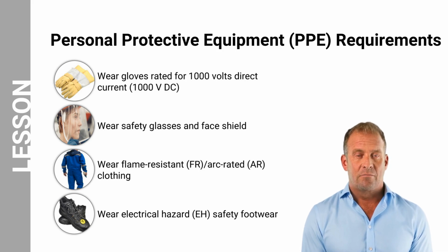Let us now look at the requirements to ensure you are safe when working on high-voltage systems. Wearing appropriate personal protective equipment that includes gloves rated for 1,000 volts direct current, safety glasses and face shield, flame-resistant and arc-rated clothing, and electrical hazard safety footwear is crucial to ensure the safety of technicians.